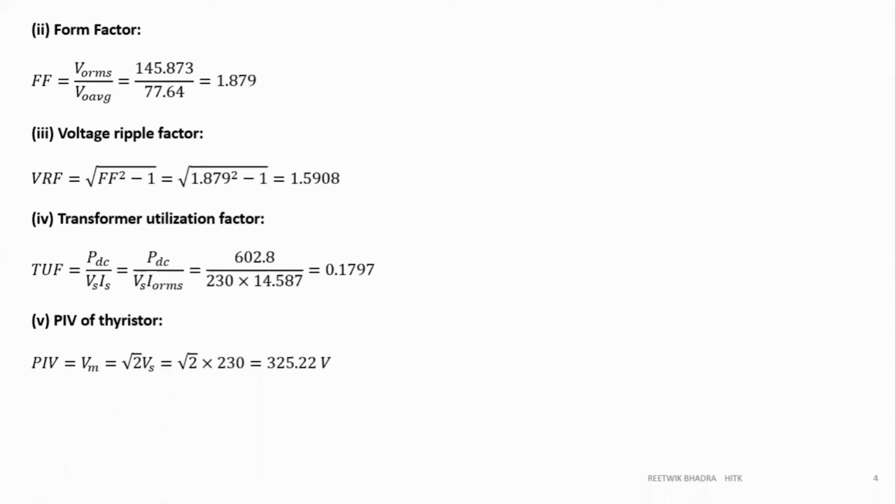When we buy a thyristor, it's very important to check the current and voltage rating, the forward bias one, as well as the reverse bias rating also. Because sometimes it may be subjected to reverse bias voltage, because it has to be turned off. So that rating should not be exceeded. That's why this is very important.